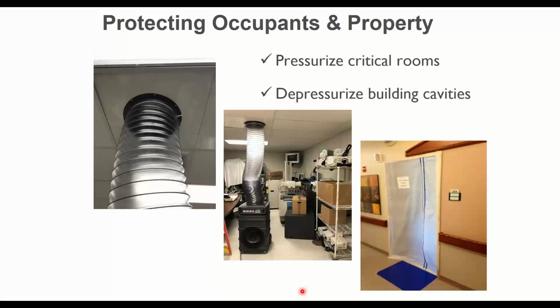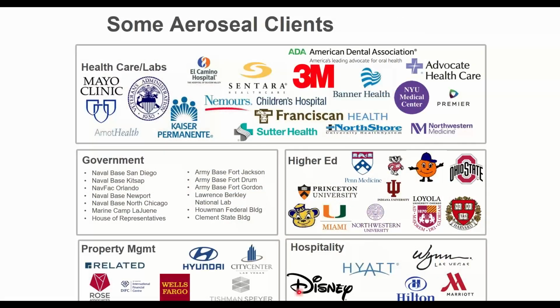So it sucks air in through high efficiency, high MERV rated filters to pull that glue out of the air, so that way you don't have it moving all over the space. This is kind of an old chart, probably from 5-6 years ago, showing you some of the high profile Aeroseal commercial clients. Since this time, there's been more and more of these added to the list, because it is a pretty common technology.